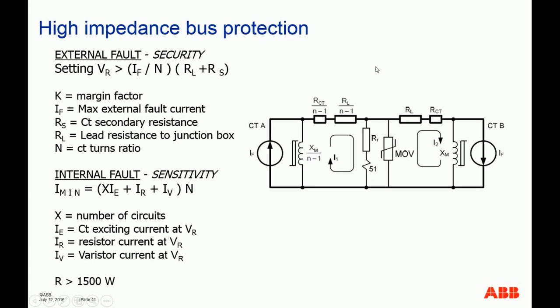analyzed. You can see here on the left-hand side there are multiple CTs connected in parallel. On the right-hand side is one CT, so we call them CTA and CTB. In fact, CTA is a group of CTs connected in parallel. You can see the polarity of these two perfect current sources that represent the CTs. They are actually in the same direction. That would mean we are talking about an external fault. So during the external fault, the current flows this way.